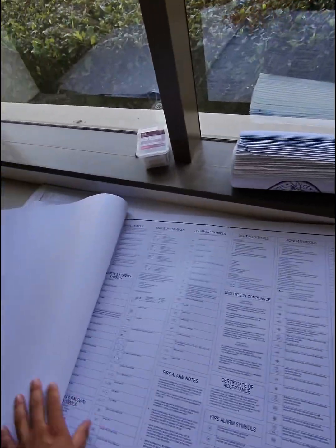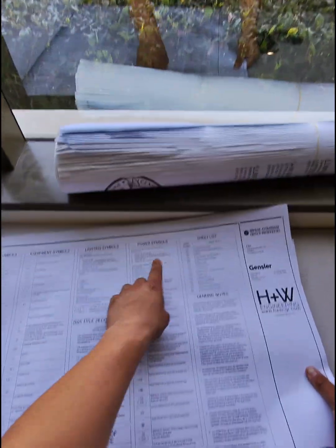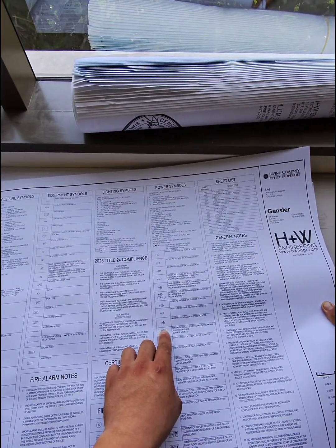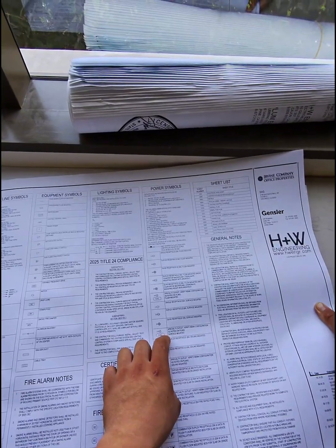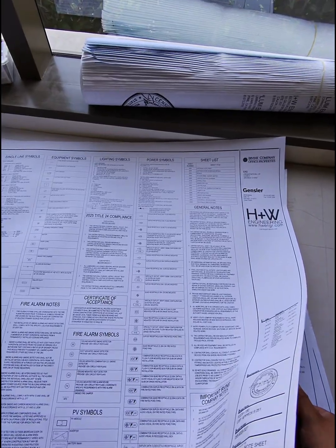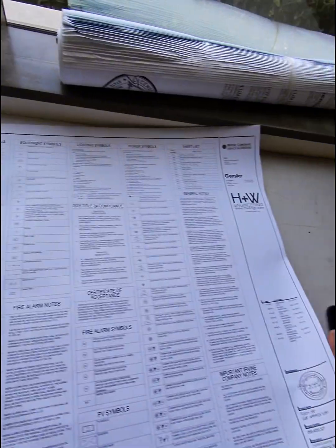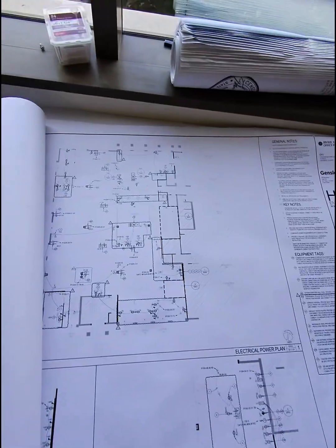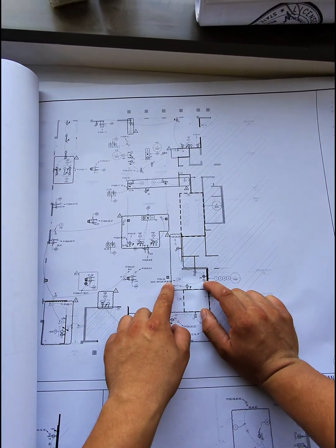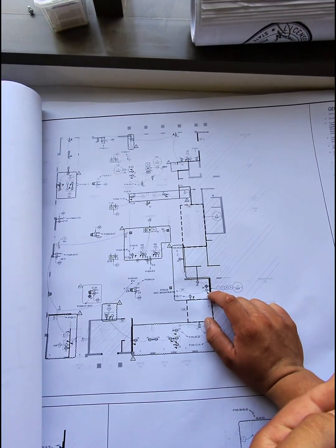So this is the electrical note sheet, and these are the power symbols. If I look at that symbol that was referenced, it's a specialty outlet. Verify NEMA configuration is notated on plans. So it's a special outlet. Let me make sure it's not anywhere else. When I look at the power plan and reference that outlet here, it shows 1 hot, 1 neutral, and 1 ground. So a part of me can make that a single gang or a 2 gang.